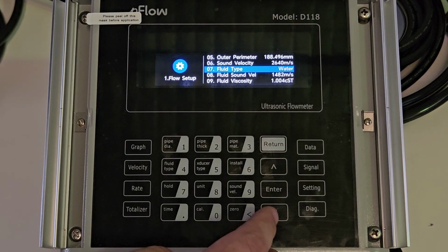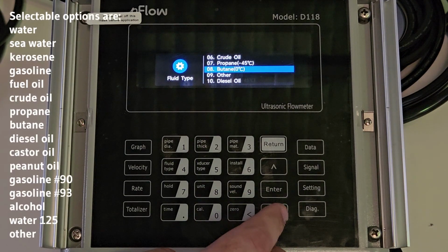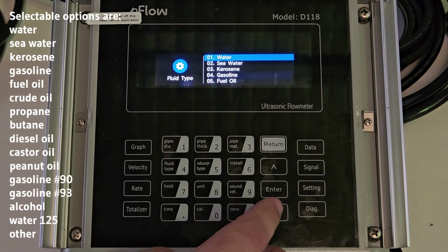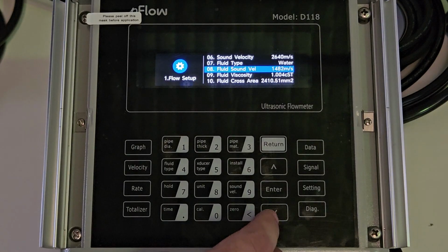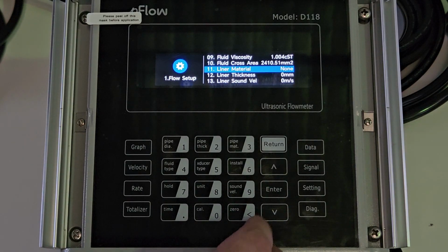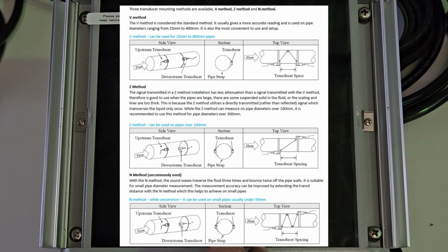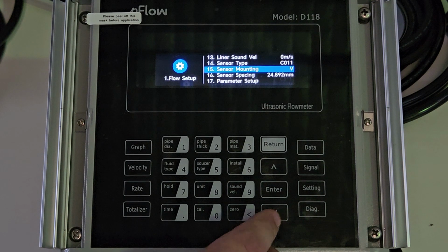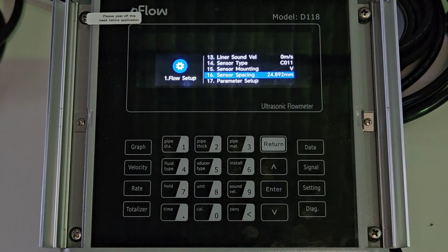Scroll down until you reach fluid type. Press enter and scroll the list for your fluid. In this case, I have selected water. Continue pressing down to go through the configuration steps. If you have a pipe liner, you can input the details here, or select none and 0 mm thickness. Sensor type should generally be set as the default C011 unless you have a different model or perhaps high temp sensors. Sensor mounting, we are using the most common and easy to use V method, but other methods are available and can be selected here. Now down one more time and you can see the required sensor spacing, 24.892 mm in this case. Take note of this to gap the flow sensors accordingly.